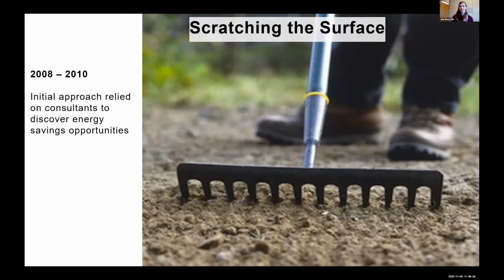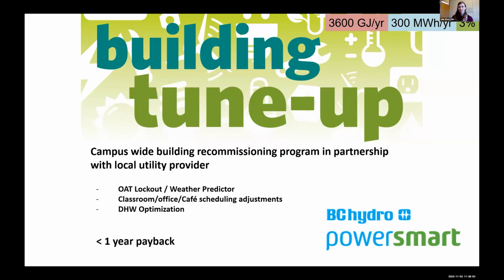In the initial approach for energy conservation on campus, we relied heavily on consultants to do energy savings opportunities. Those were a result of the eco-trek years, and we were really just scratching the surface on what we could do on campus. The initial approach took partnering with BC Hydro and doing a campus-wide building tune-up program through their incentive system, and we were able to do a lot of simple controls changes in the buildings, not just life sciences, but across campus: things like outdoor air temperature lockout, weather prediction, classroom/office/cafe scheduling adjustments, and optimizing domestic hot water systems. We found that these had less than a 1 year payback in this building in particular, and saved roughly 3% alone on its energy consumption, roughly 3,600 gigajoules and 300 megawatt hours of electricity use.